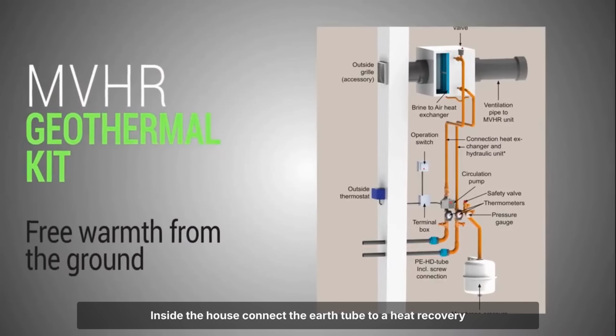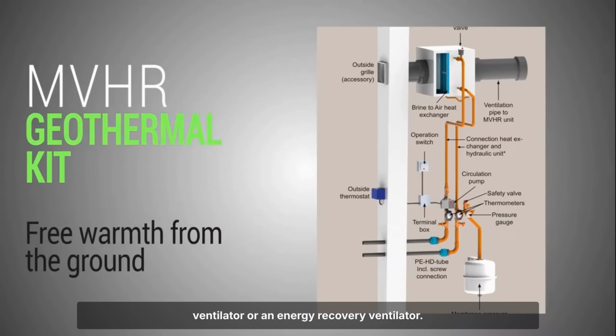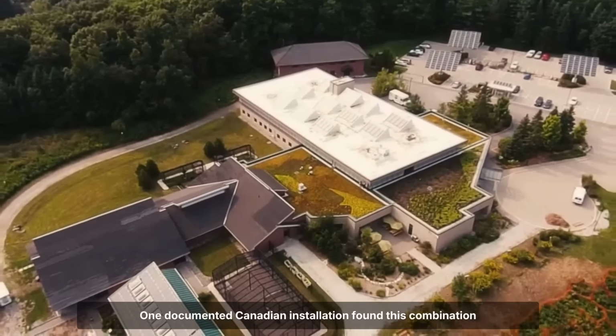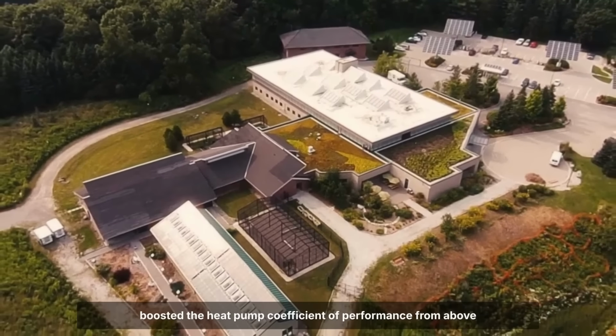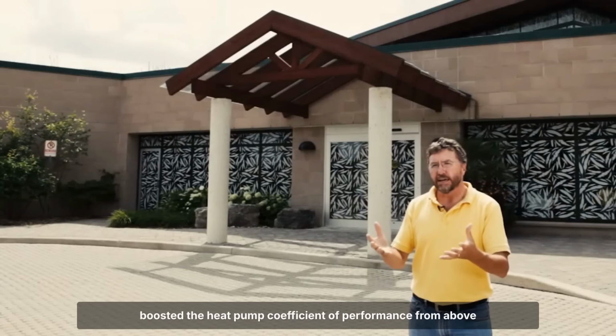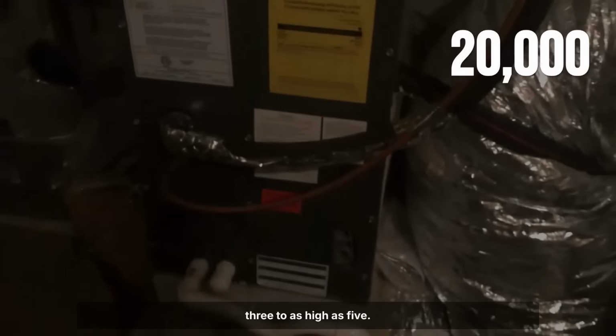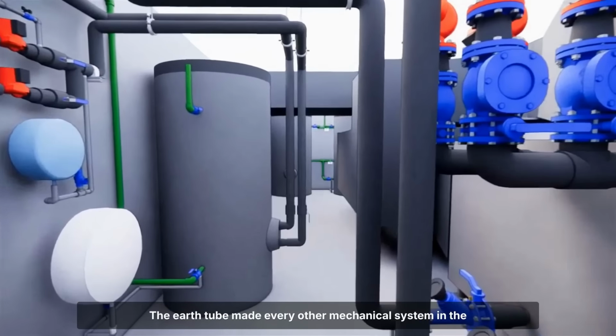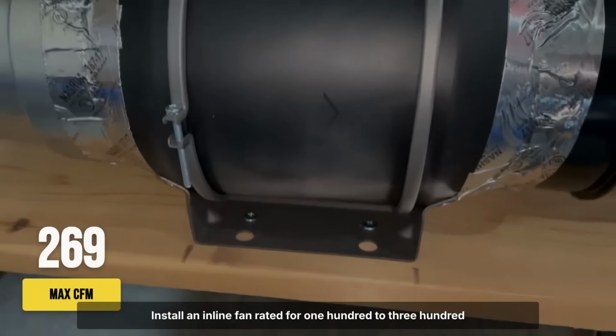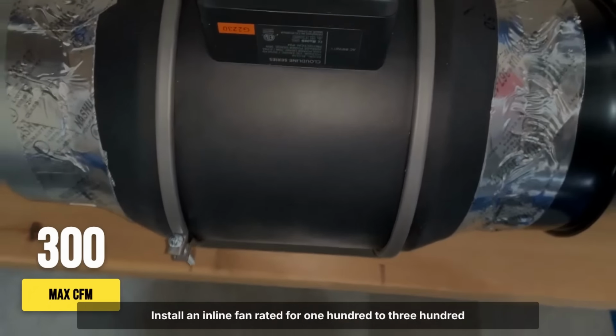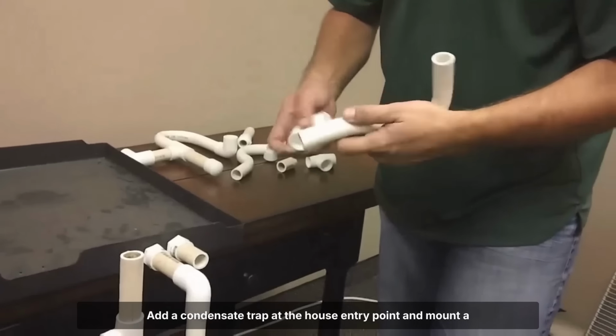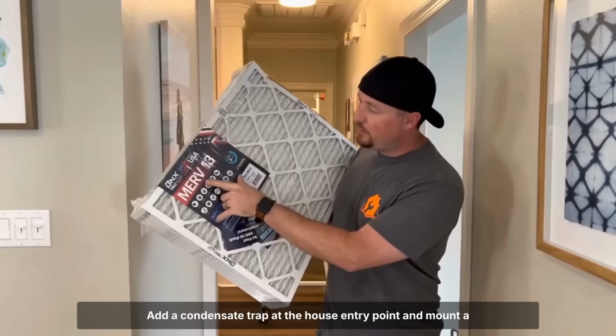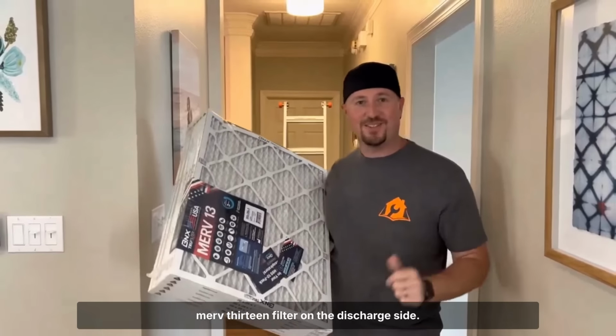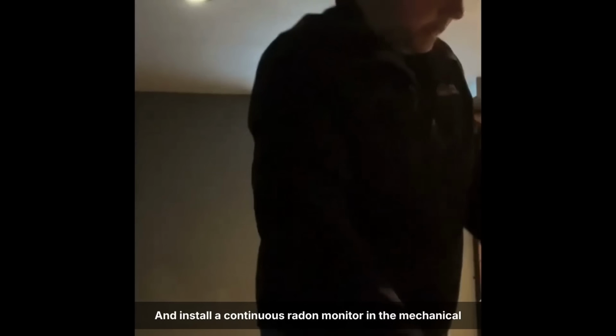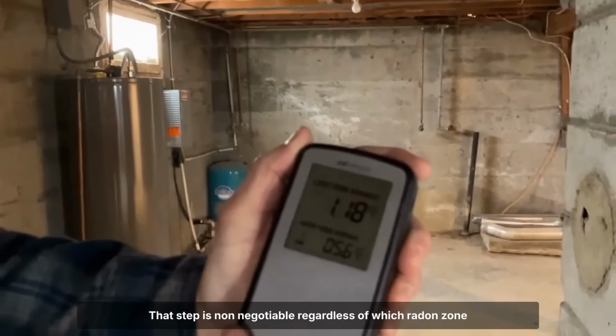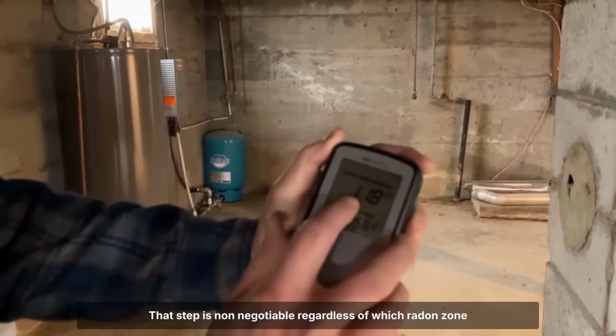Inside the house, connect the earth tube to a heat recovery ventilator or an energy recovery ventilator. One documented Canadian installation found this combination boosted the heat pump coefficient of performance from above 3 to as high as 5. The earth tube made every other mechanical system in the house work better. Install an inline fan rated for 100 to 300 cubic feet per minute. Add a condensate trap at the house entry point and mount a MERV 13 filter on the discharge side. And install a continuous radon monitor in the mechanical room. That step is non-negotiable regardless of which radon zone you live in.